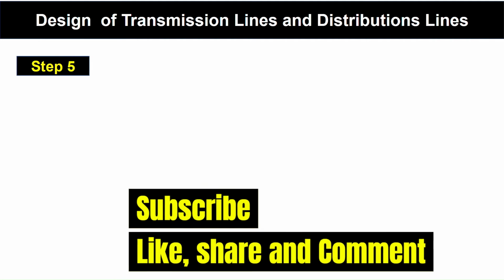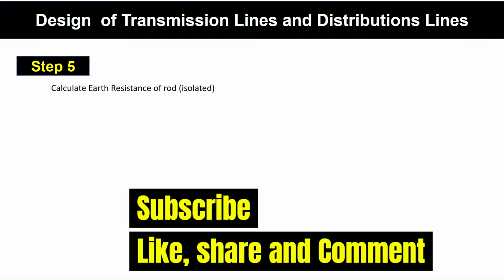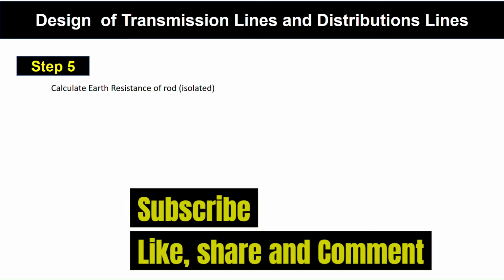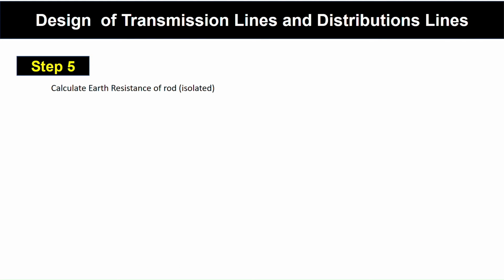Step 5. Calculate earth resistance of a rod. Isolated rod, we have to calculate the earth resistance of one rod. Re, that is the earth resistance of a rod, equals rho divided by 2 pi L into log of 8L divided by D minus 1.